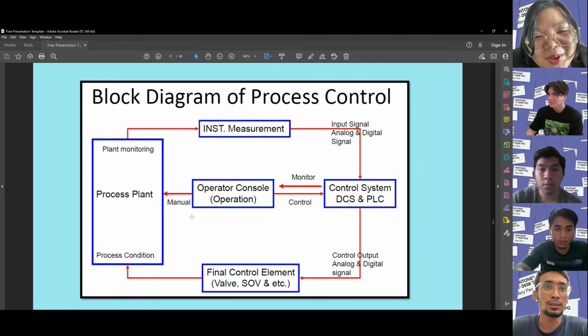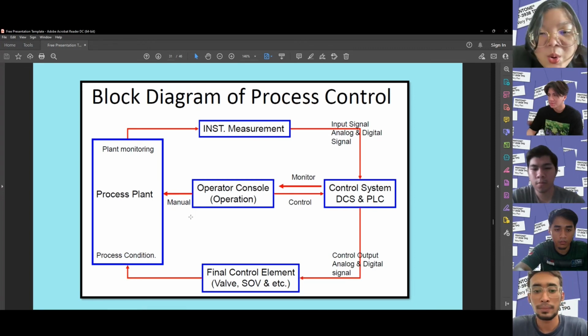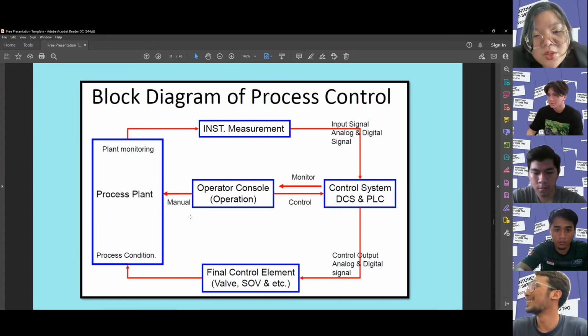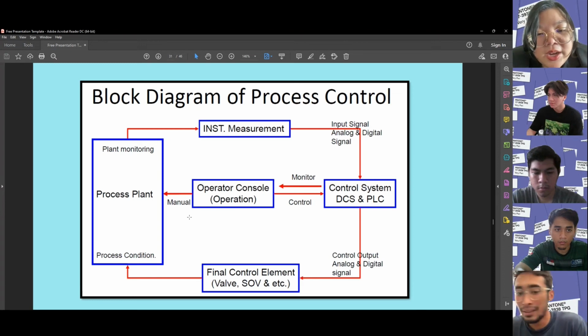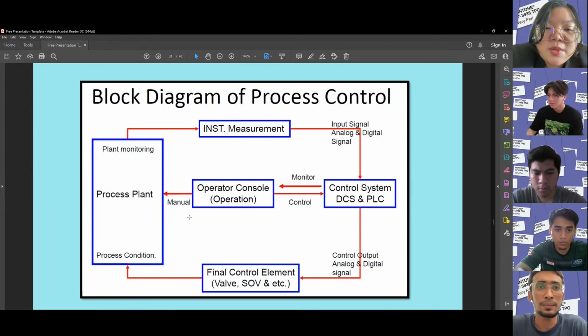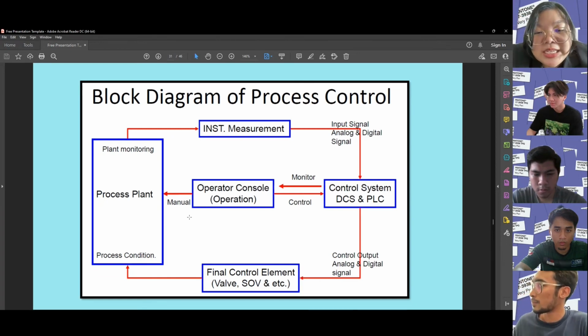Next. Okay, for the block diagram of the process controller. First, they use the instrument measurement, and then it goes into the control system, which is DCS and PLC, and then to the operator console, where the operator monitors. After that it goes to the process plant, which is monitored, and the process of the plant itself goes into the instrument measurement. Another type is they go through the DCS or PLC and straight to the final control element, which is a valve, then straight to the process plant and back to the instrument measurement.